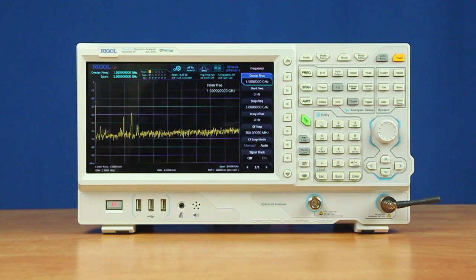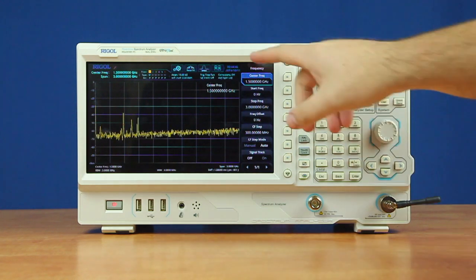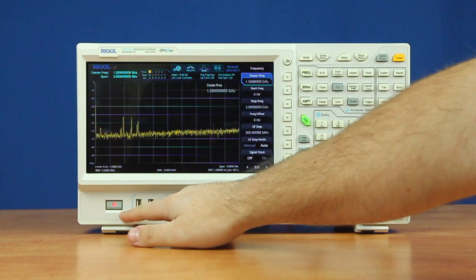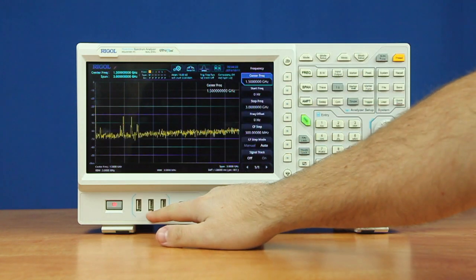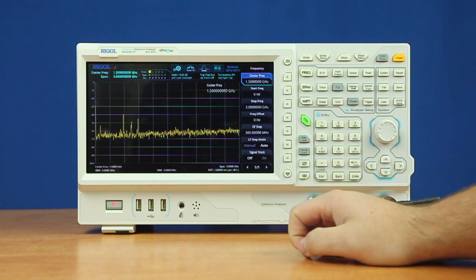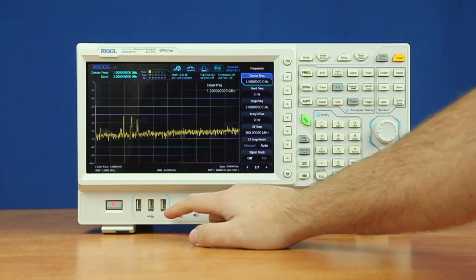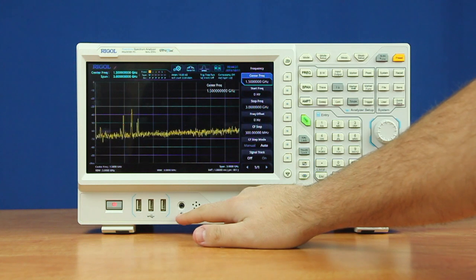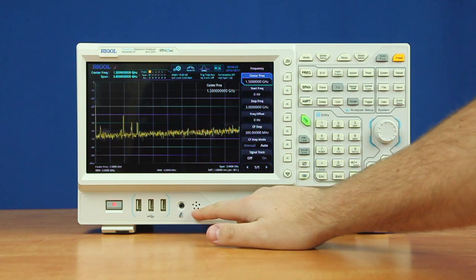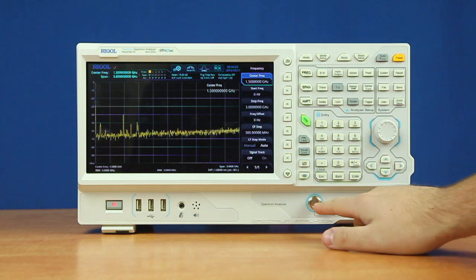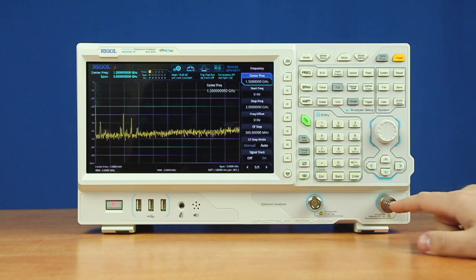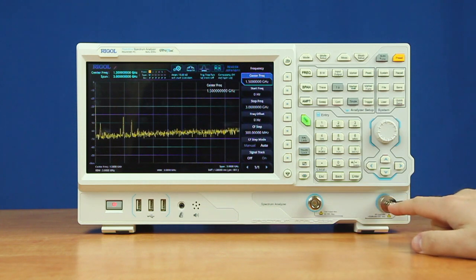On the front panel of our instrument we have a 10.1-inch touchscreen display. Below that we have our power button followed by three USB ports which can be used for a wired keyboard and mouse along with a flash drive all at once. Then we have a headphone jack output, a speaker output, our optional tracking generator output, and then the input for our spectrum analyzer.